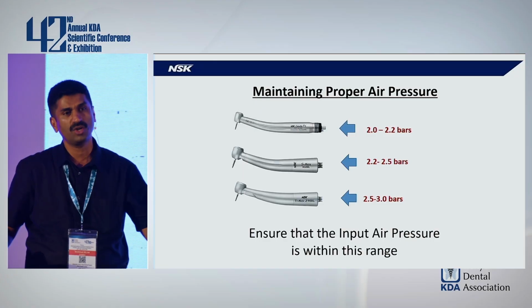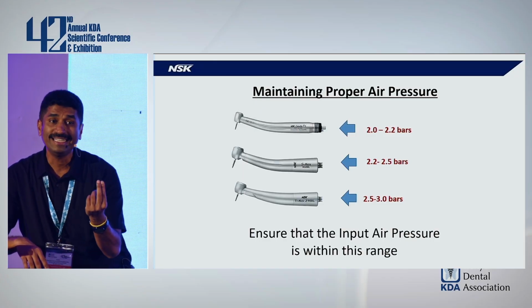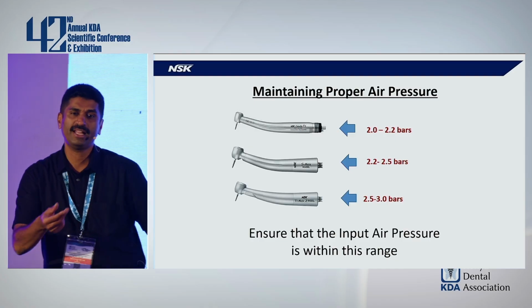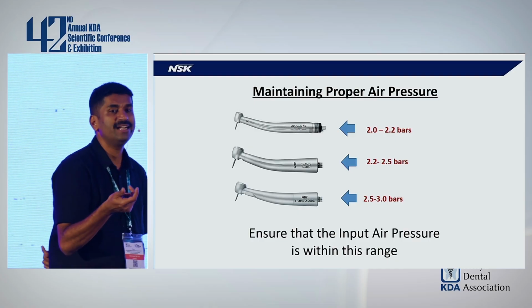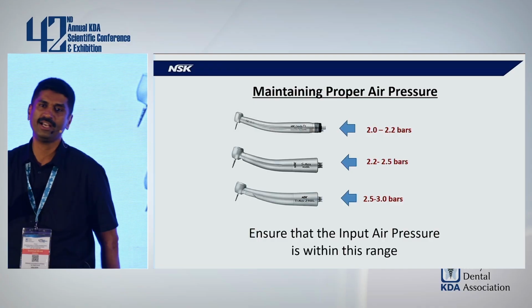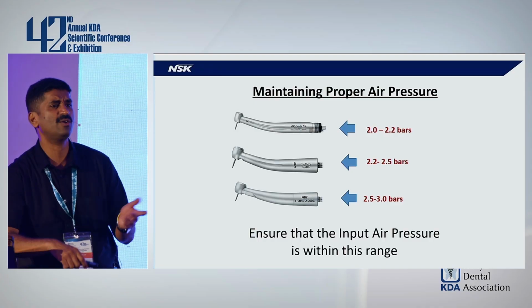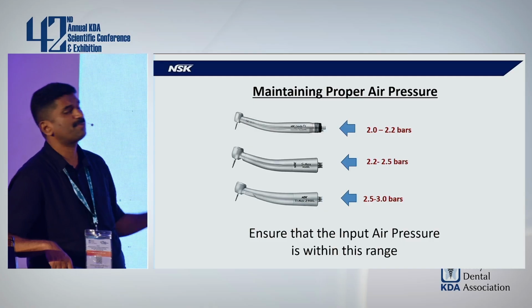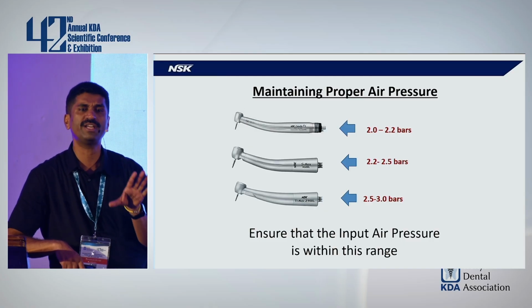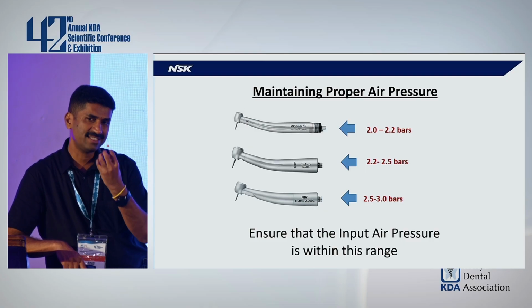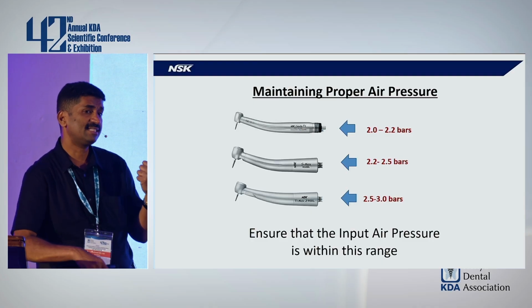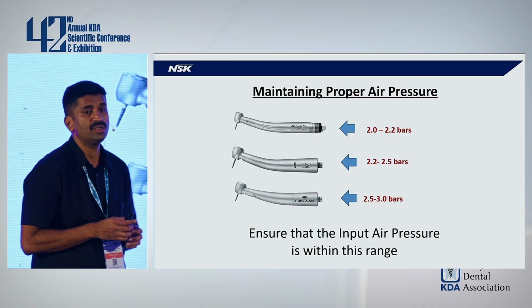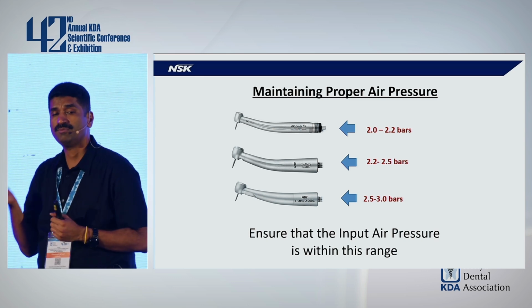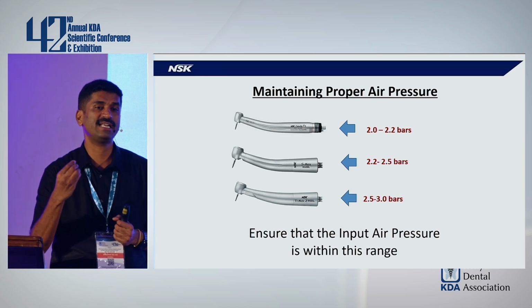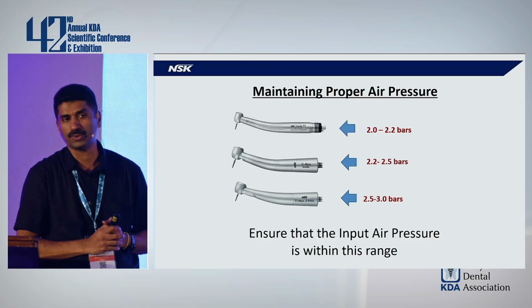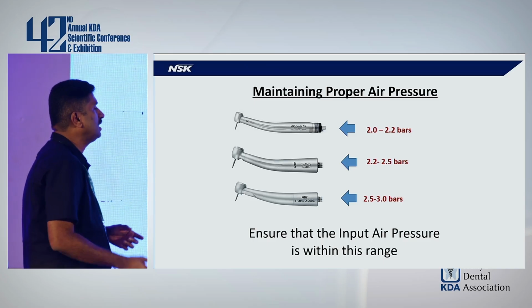What to do? Call the engineer and get the compressor drained. Each and every compressor will have a drain valve which needs to be opened at regular intervals, depending on the make of the compressor. It may be once a week, once a month, or whatever. So you can do this practice maybe once a week or once a month just to ensure that the handpiece is only taking pure air. This test will ensure not only the long life of the handpiece, but also that such dust particles don't go into your patient's mouth. So that plays a very important role.